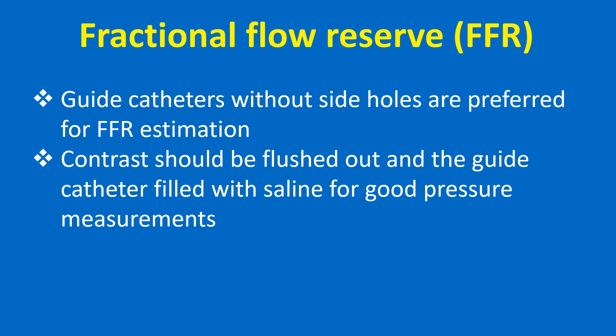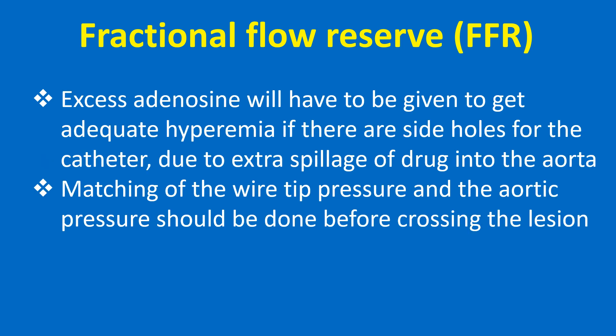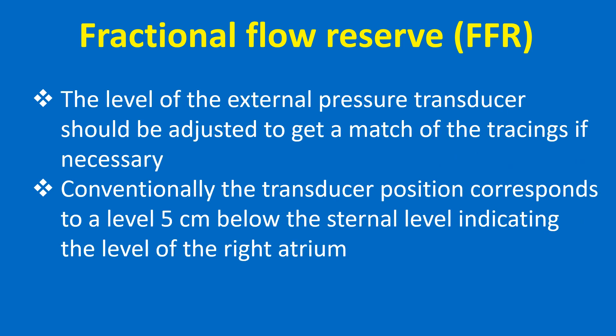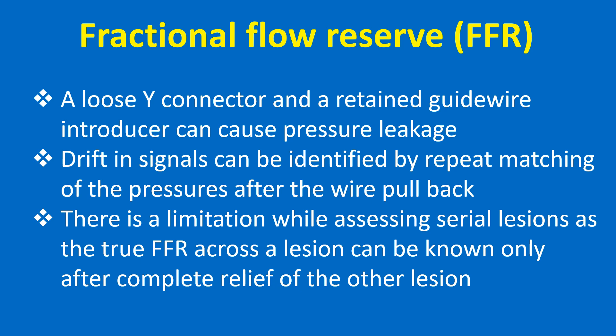Guide catheters without side holes are preferred for FFR estimation. Contrast should be flushed out and the guide catheter filled with saline for good pressure measurements. Excess adenosine will have to be given to get adequate hyperemia if there are side holes in the catheter due to extra spillage of drug into the aorta. Matching of the wire tip pressure and the aortic pressure should be done before crossing the lesion. The level of the external pressure transducer should be adjusted to get a match of the tracings if necessary. Conventionally, the transducer position corresponds to a level 5 cm below the sternal level, indicating the level of the right atrium. A loose Y-connector and a retained guide wire introducer can cause pressure leakage. Drift in signals can be identified by repeat matching of pressures after wire pull-back.